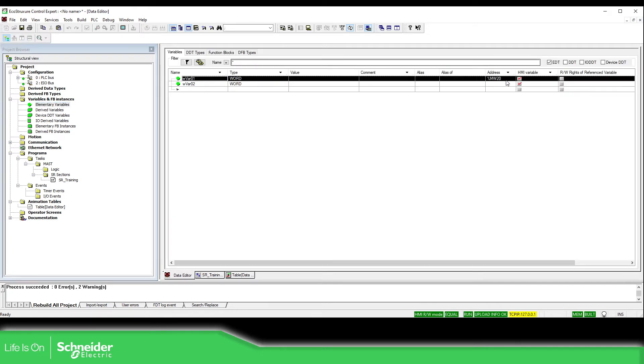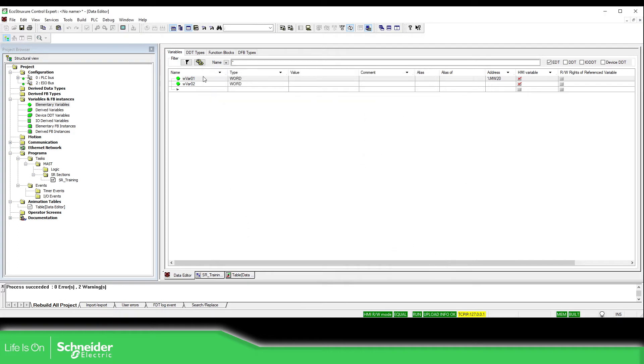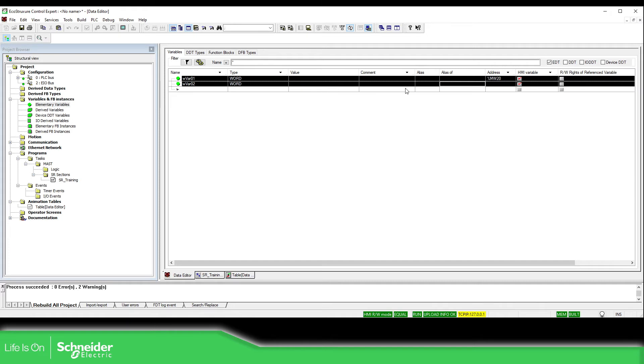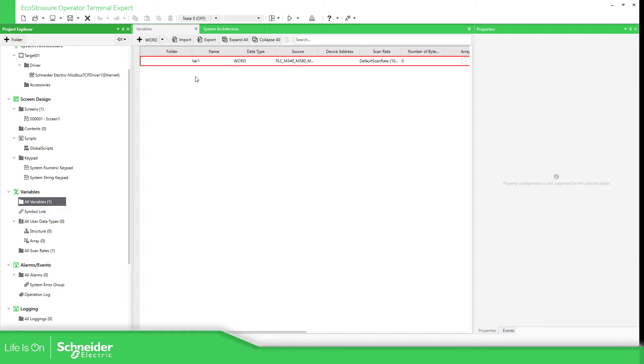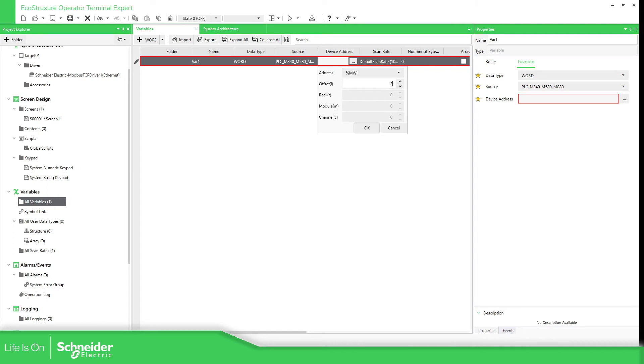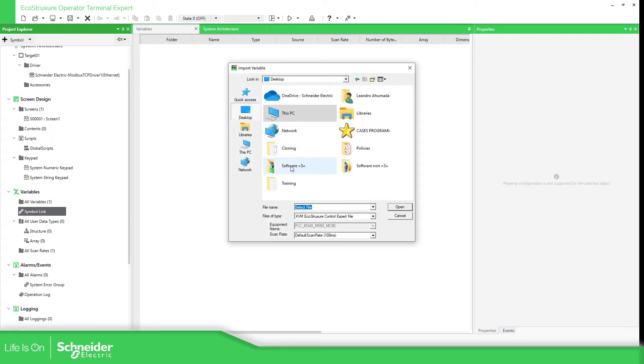We just need to define the values that you want. If you want to use address, select address, and then what you need to do is select the HMI variable. On Tools > Project Settings, remember to use in the PLC embedded data: Data Dictionary and only variables. Select the one that you want to export — right-click and export selected. So the other way I showed you: if you want the variables, just need to go here and add it. Click w_var_01 direct. And then the other way is to use the symbol link — XVM import.